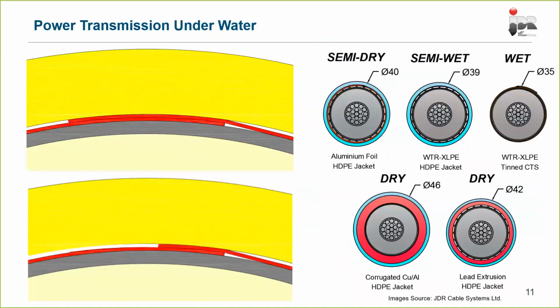Right, now in terms of putting cables underwater, most of us will know that water permeates through plastic. It's an unfortunate fact, but it's one that we need to deal with. So we've got multiple different designs that we can offer, and that is known in industry. Now, what we could do is put some sort of metallic barrier, and that's what these 2 designs are about. So you might have a metallic corrugated layer over the core, or you might have a lead extruded jacket. Now, both of those are there to try and fully enclose the cable and prevent water from permeating through. However, they're very, very large, and they're quite stiff, as you can imagine. So we look at different ways where we can minimize or mitigate against water permeation through, and we'll play around with the layers that we apply.